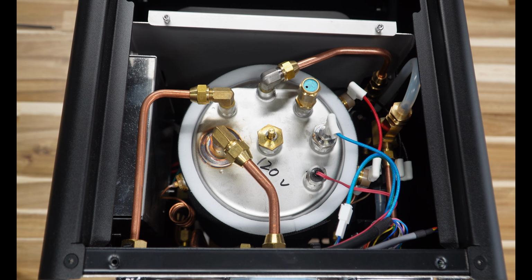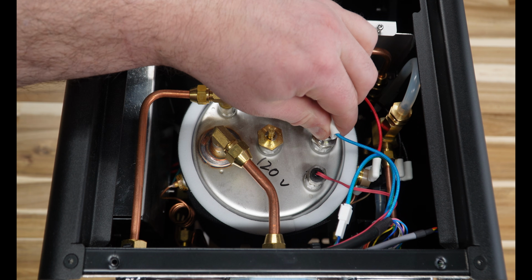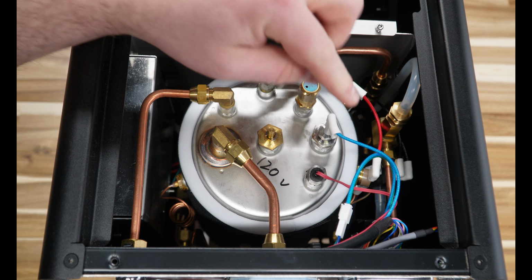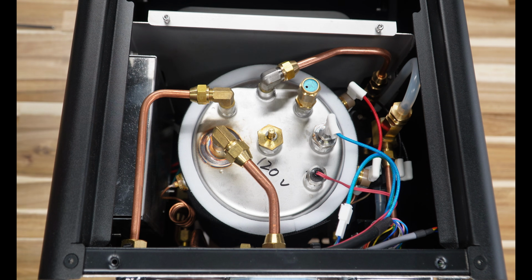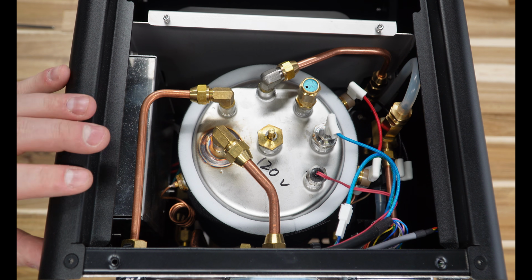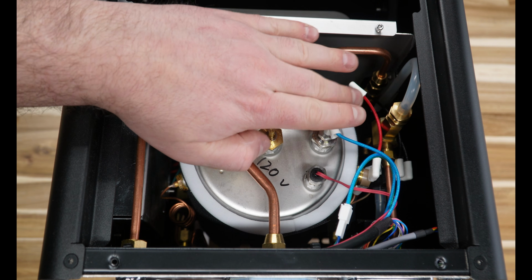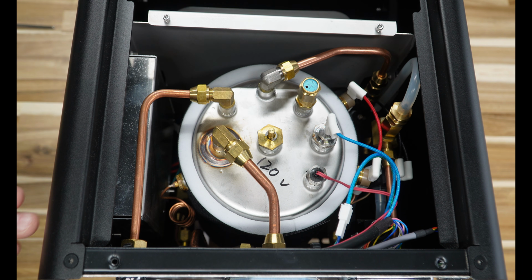Okay, so with that lid taken off, you do get access to some of the more common things that you're going to usually mess with. You do have your boiler fill probe. This probe sticks down into your tank and it conducts water. So it knows when it has a connection through the water that it is full, and it turns off your fill valves. When the pressure drops, that tells it to refill.